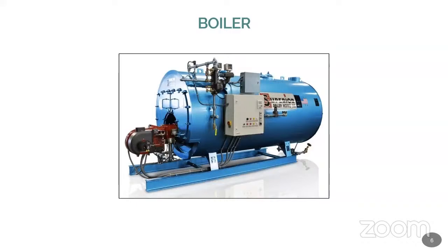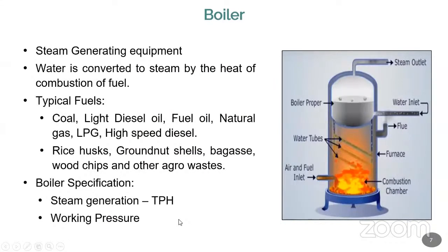Now that condensate will normally be taken back for usage, back to the boiler application. We will discuss why the condensate should be taken back and why it is so important. So this is the second cycle. In the first cycle, water is boiled and produces steam, and that steam is transmitted to the process. After the process, the condensate water goes back to the boiler feed water tank. Okay, so this is the second cycle. The entire loop has many energy conservation and energy saving possibilities. We will see them one by one. First of all, we will discuss what is meant by a boiler, why it is important, how it takes the fuel and all those things. Then we will go one by one.